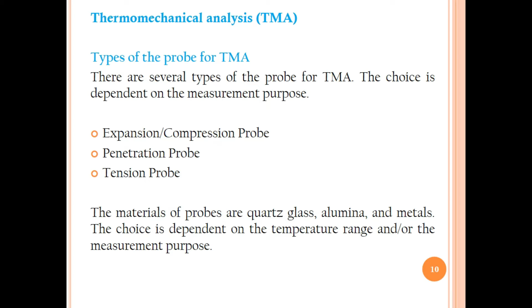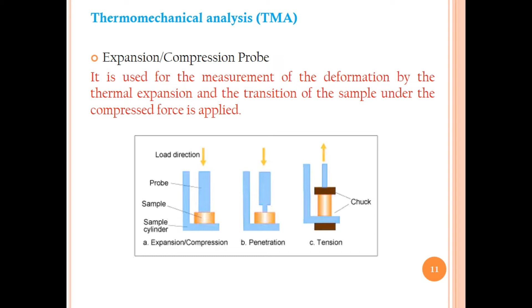The expansion or compression probe is used for the measurement of deformation by thermal expansion and the transition of the sample under the compressive force applied. In figure A, expansion compression probe, the probe is applied on the sample. One is the sample cylinder that's holding the sample, and blue is the probe, and the load direction is vertical on the sample. This type of probe is called the expansion compression probe. We use it when we want to do different experiments with different materials in the TMA technique.